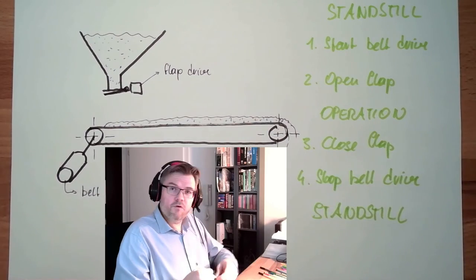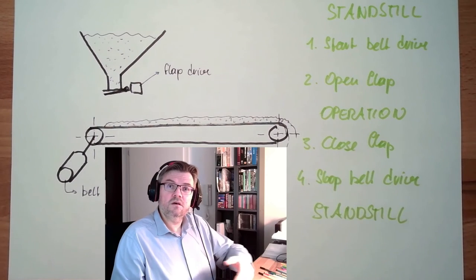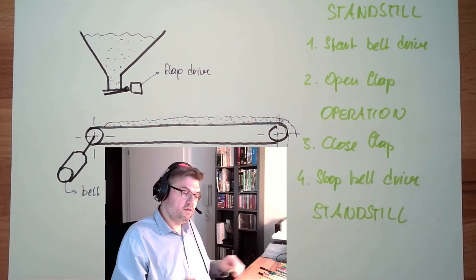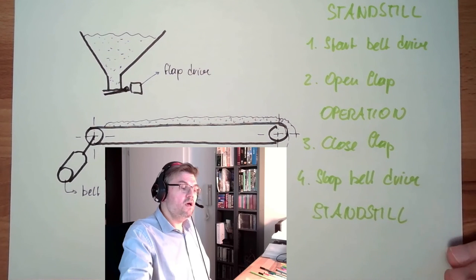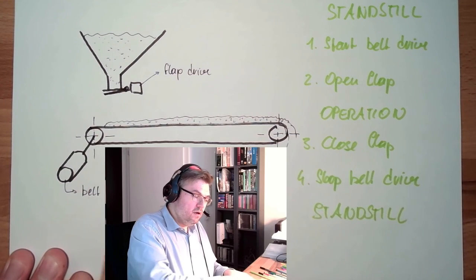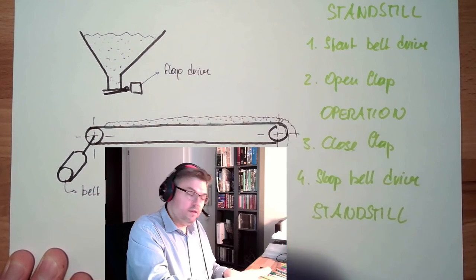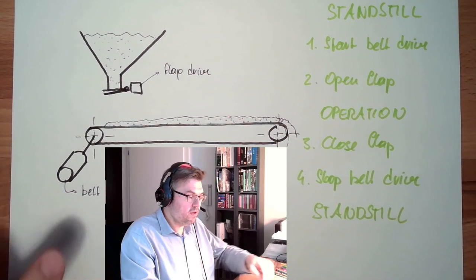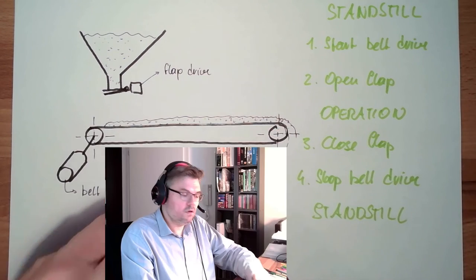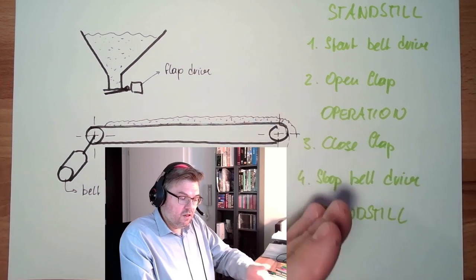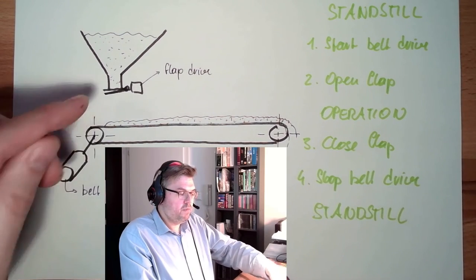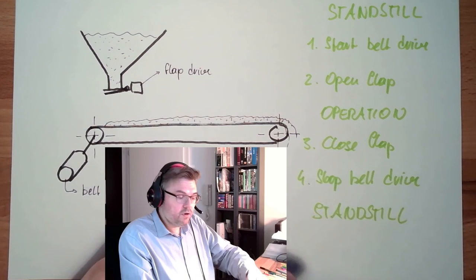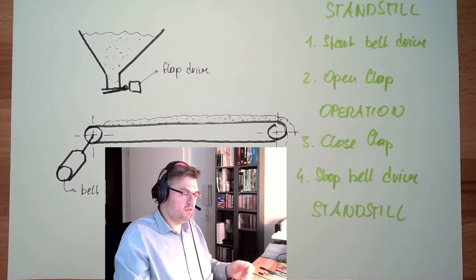With these few words, with this textual description and this layout, you know what I want from here. I want that we can go from standstill to operation, from operation to standstill. And the procedure is to first start the belt without load, that it's light or easy for the belt drive to run, to start running. Then we start loading, then we are in operation. When we unload or when we go to standstill, we shall close first the flap, then the belt is unloaded and then we stop the belt. That's it.